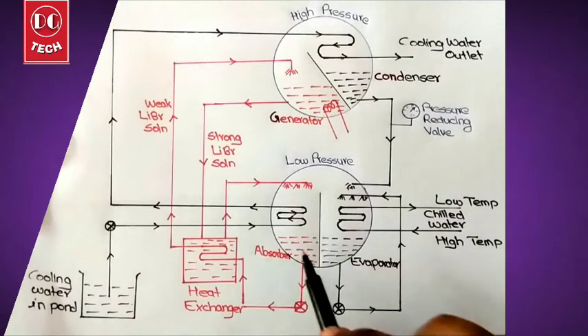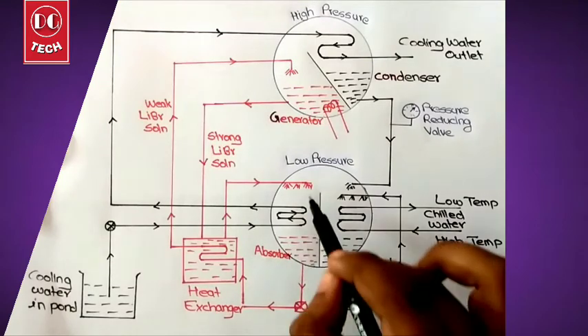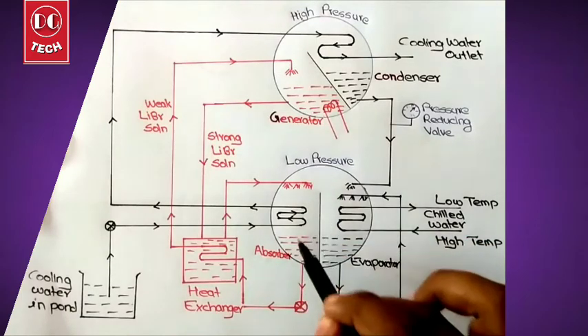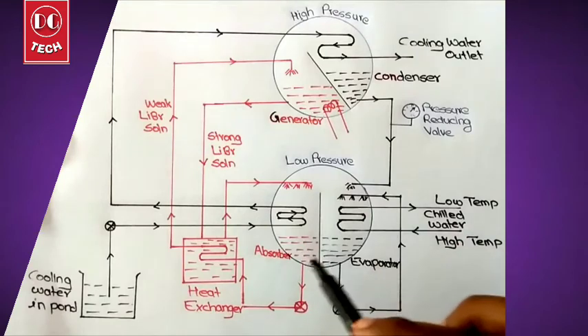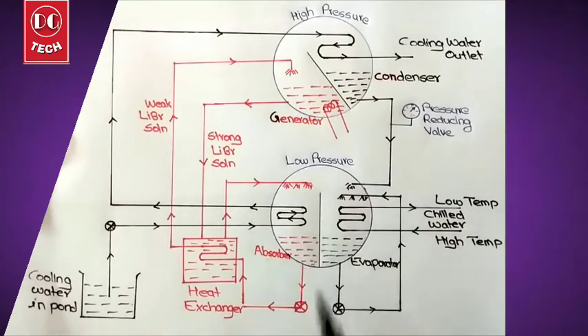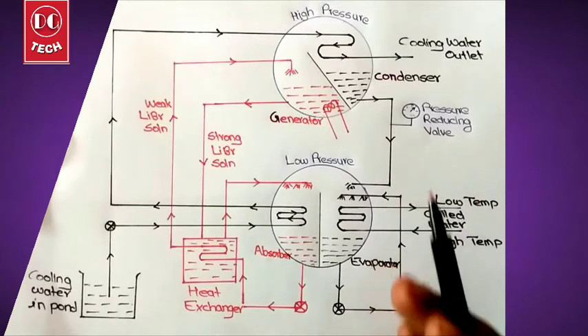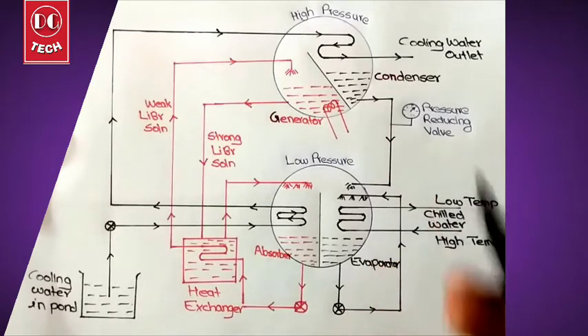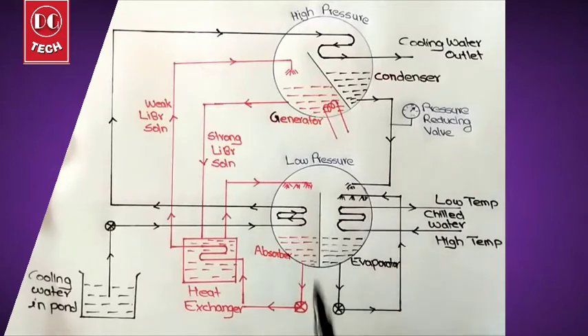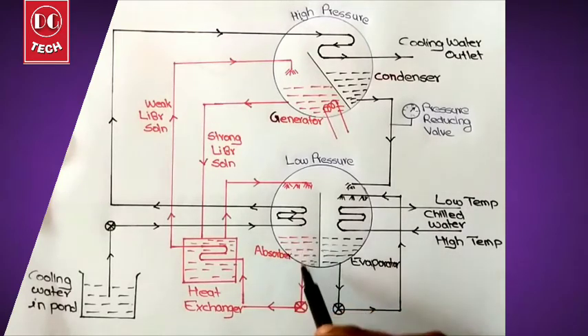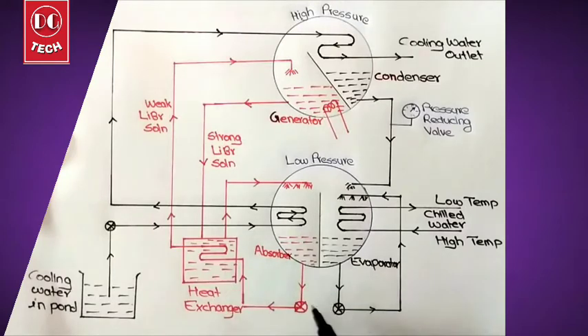In the absorber, it is filled with lithium bromide. The lithium bromide will absorb water vapor and it will get mixed. Such a mixture of lithium bromide and water is known as a weak mixture, because the water content in the lithium bromide is high—it is not strong lithium bromide. This weak lithium bromide is fed into the heat exchanger using a pump.